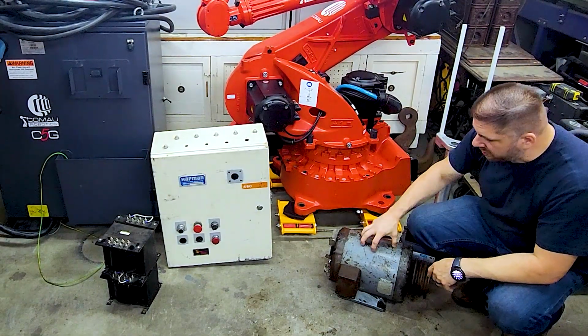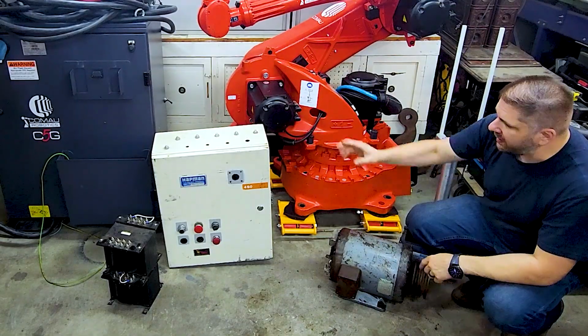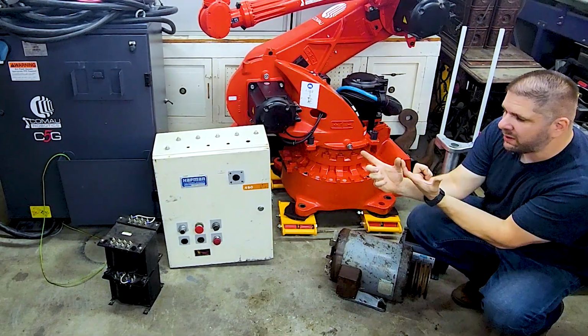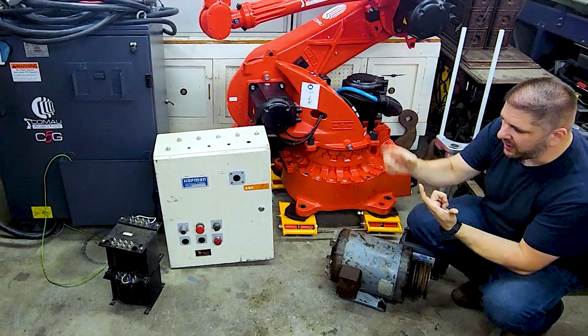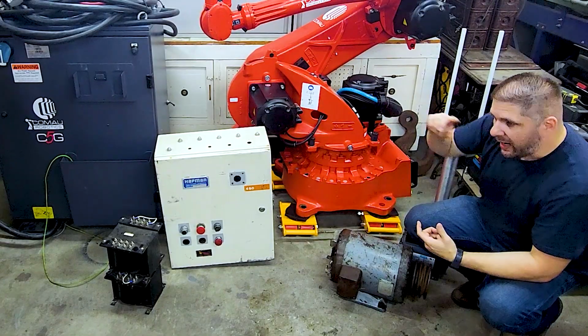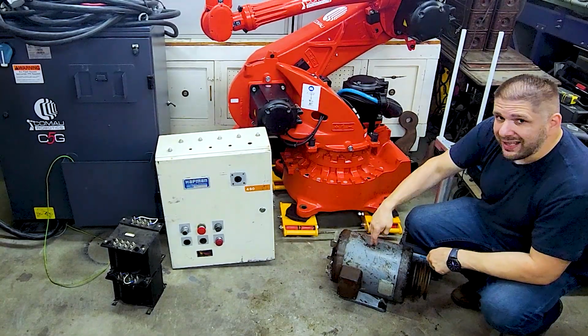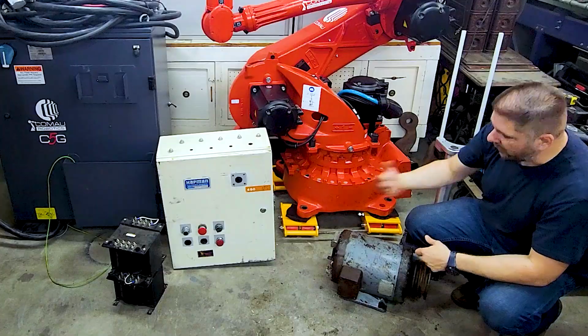So what this motor is doing is I'm working it like a motor generator. Inside there are those capacitors that go across the two different legs of this three-phase motor. So I have single phase going into the two outer legs. And when it gets spinning, the center phase is generated. And that generated phase is what goes out.